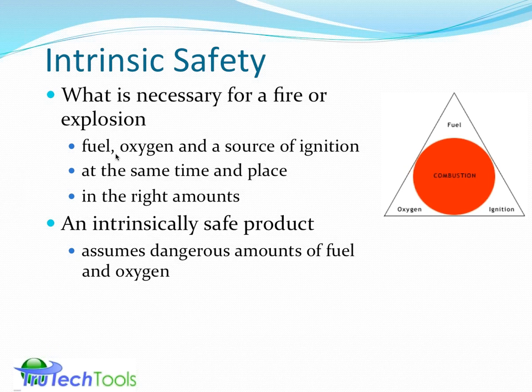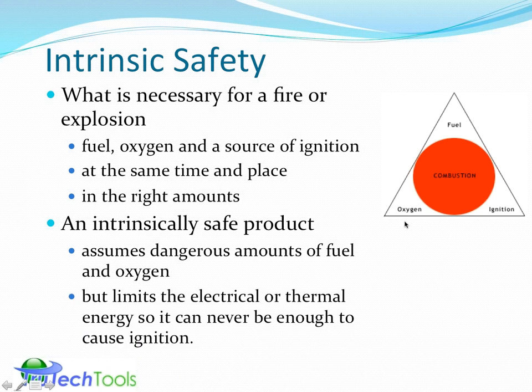So an intrinsically safe product assumes that you have two of these items, the fuel and the oxygen, in quantities that can lead to combustion or can lead to explosion. It assumes that that could happen, and therefore it limits the thermal energy in the product or the electrical energy so there can never be enough energy. So it controls this one leg of the triangle. That's what an intrinsically safe product does. That's what it brings to the game.